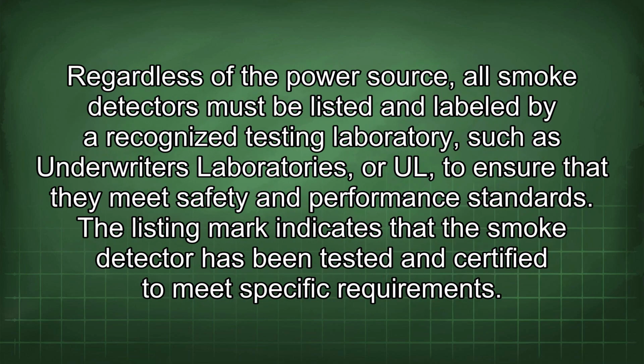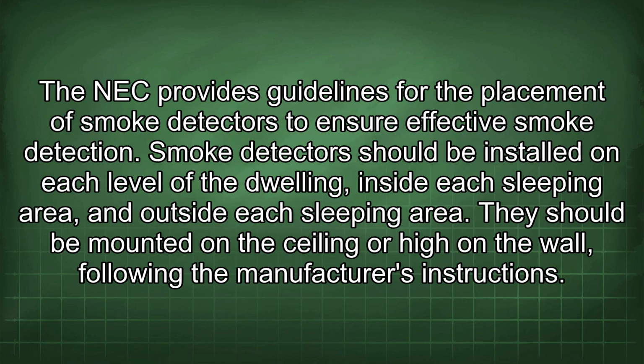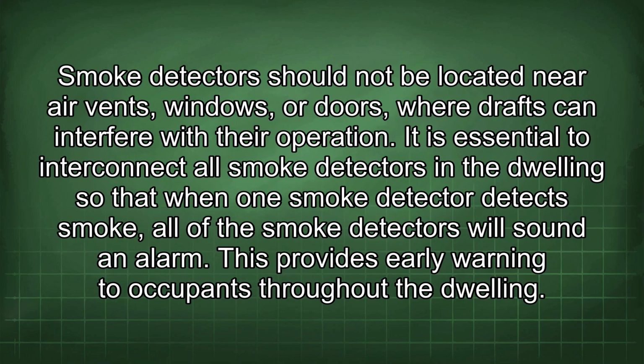Regardless of the power source, all smoke detectors must be listed and labeled by a recognized testing laboratory, such as Underwriters Laboratories, or UL, to ensure that they meet safety and performance standards. A listing mark indicates that the smoke detector has been tested and certified to meet specific requirements. The NEC provides guidelines for the placement of smoke detectors to ensure effective smoke detection. Smoke detectors should be installed on each level of the dwelling, inside each sleeping area, and outside each sleeping area. They should be mounted on the ceiling or high on the wall following the manufacturer's instructions. Smoke detectors should not be located near air vents, windows, or doors where drafts can interfere with their operation.